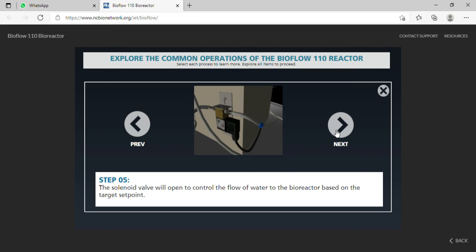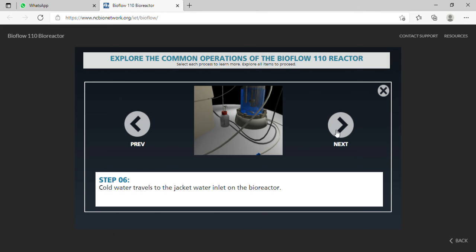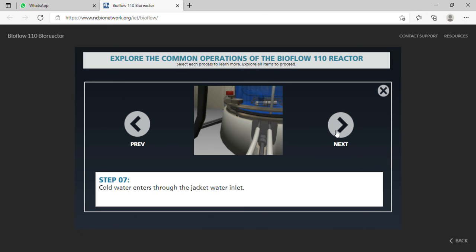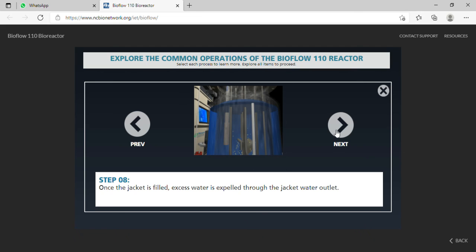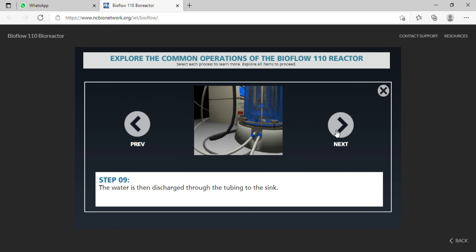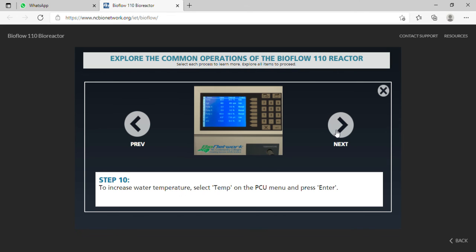Step 5. The solenoid valve will open to control the flow of water to the bioreactor based on the target set point. Step 6. Cold water travels to the jacket water inlet on the bioreactor. Step 7. Cold water enters through the jacket water inlet. Step 8. Once the jacket is filled, excess water is expelled through the jacket water outlet. Step 9. The water is then discharged through the tubing to the sink.